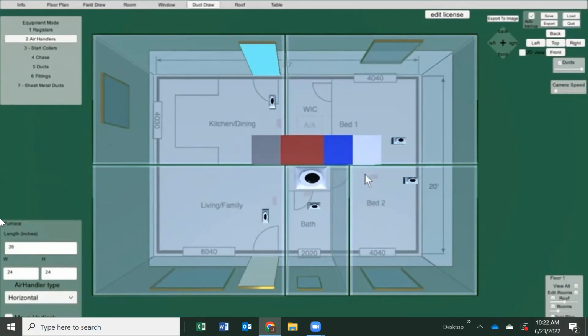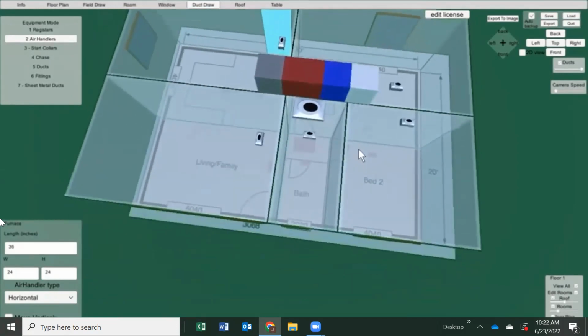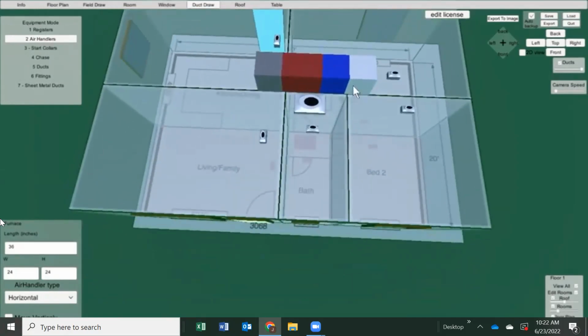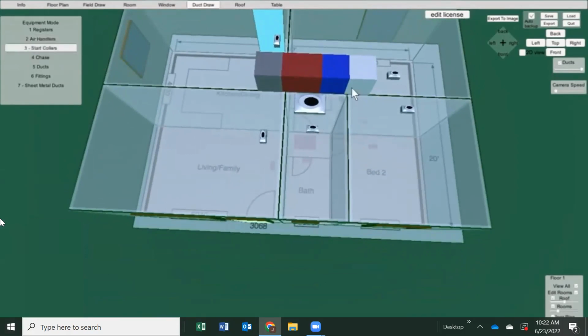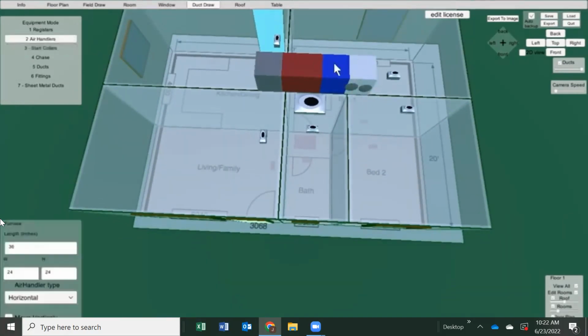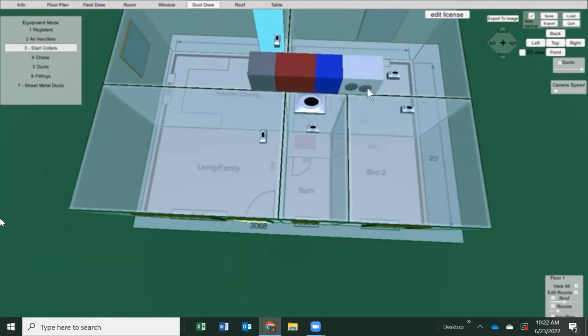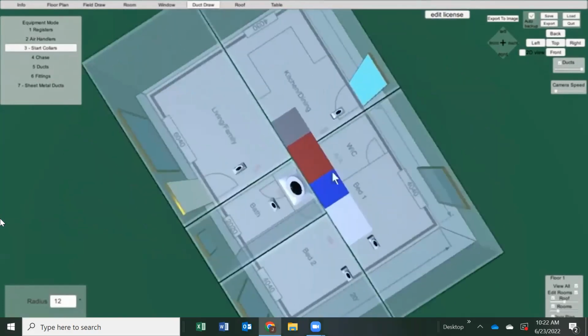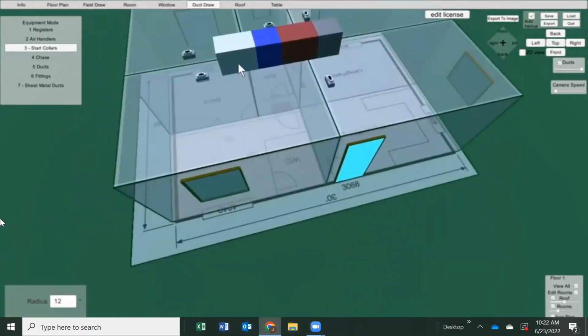So what I wanna do now is I'm gonna put start collars on the supply plenum. And click on start collars. So this is gonna have four trunks, and you'll see why later. And if that supply plenum looks a little small, just go back to air handlers, click on it. It's at 24 inches, let's make it 36, give us a little bit more room. Go back to start collars. The supply plenum is always too small. Move those around however we want to. So I know there's gonna be four trunks on this system, two on each side. I laid this out in advance, just sketched it up. How to design systems will be a different video.